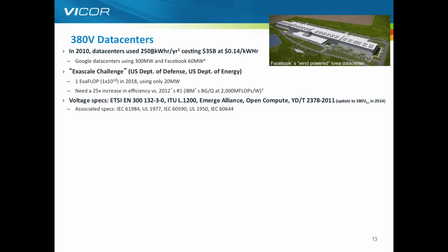Now, when it comes to voltage specs, there was a huge breakthrough probably 18 months ago now, with the publication of 2 specifications specific to high voltage DC. One coming from ETSI, that's the European Telecom Standards Institute, and one from the ITU, that's the International Telecommunication Union, which dictate exactly what we mean by 380 volts. What is the normal operating range? What is the wider operating range? And then what is an abnormal or fault condition?